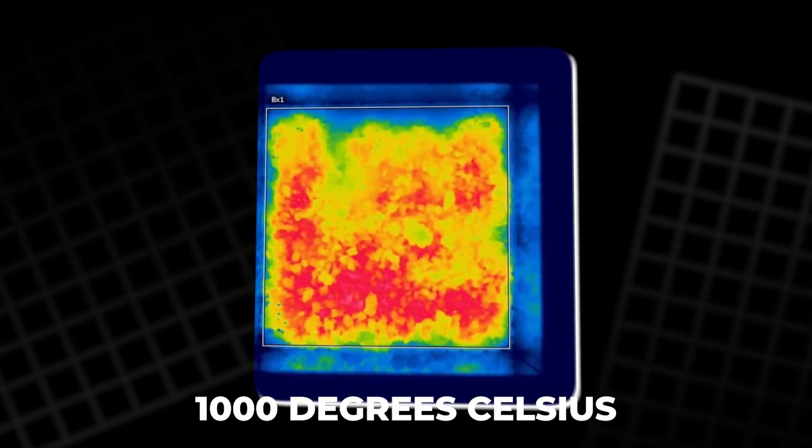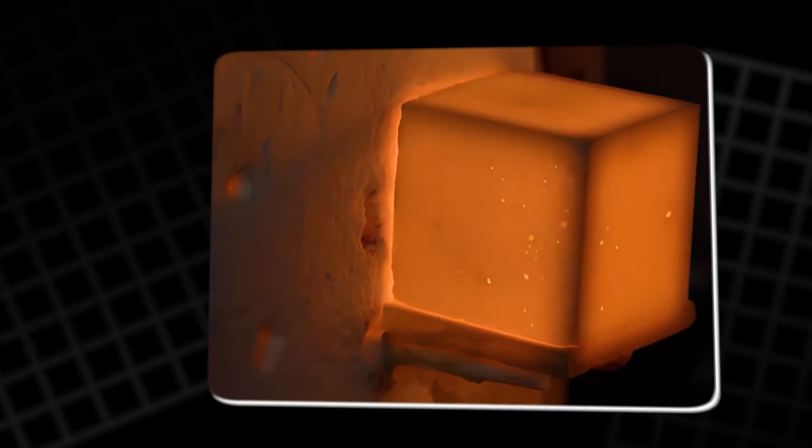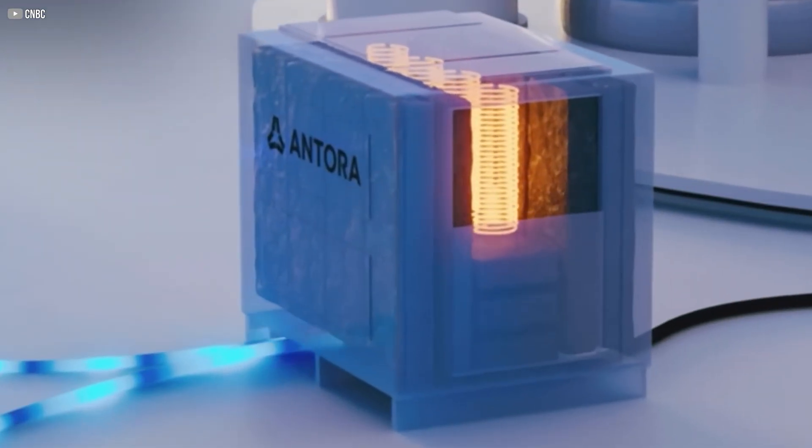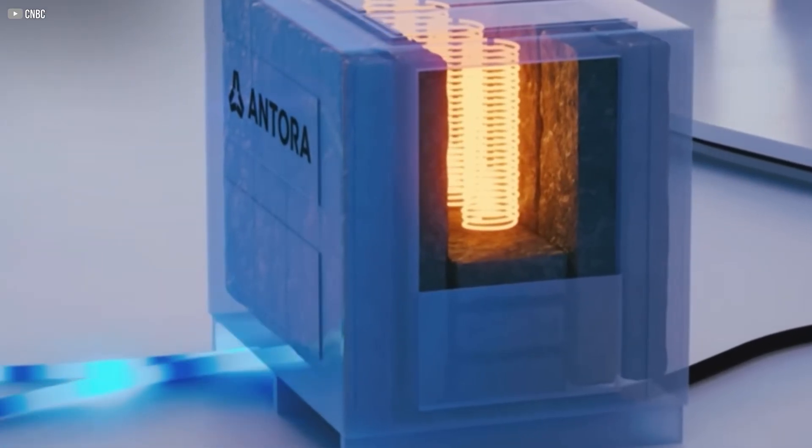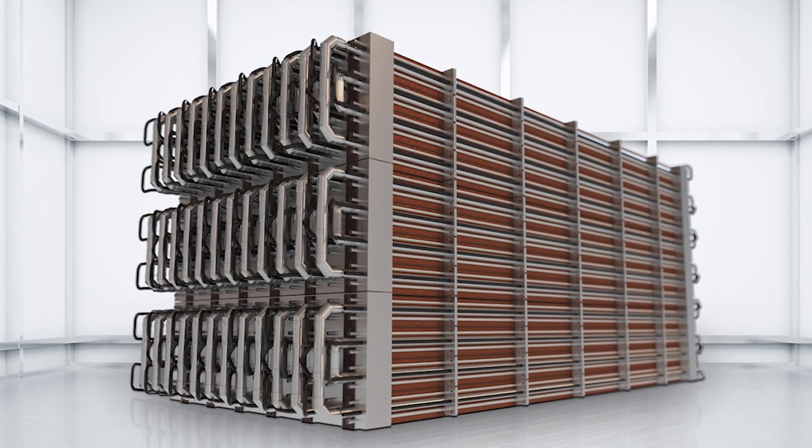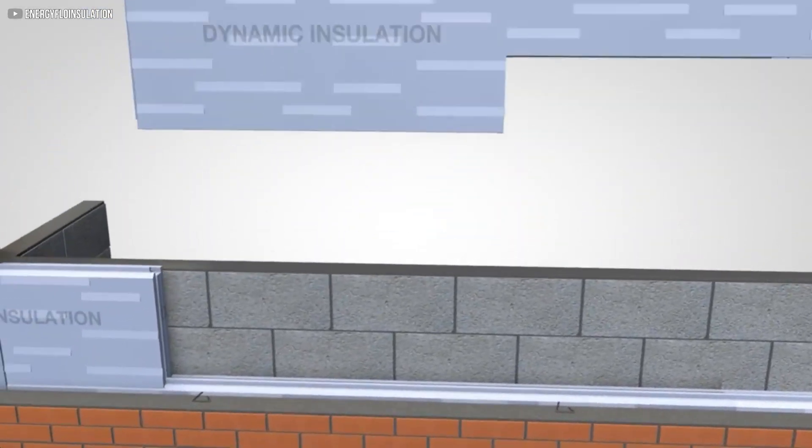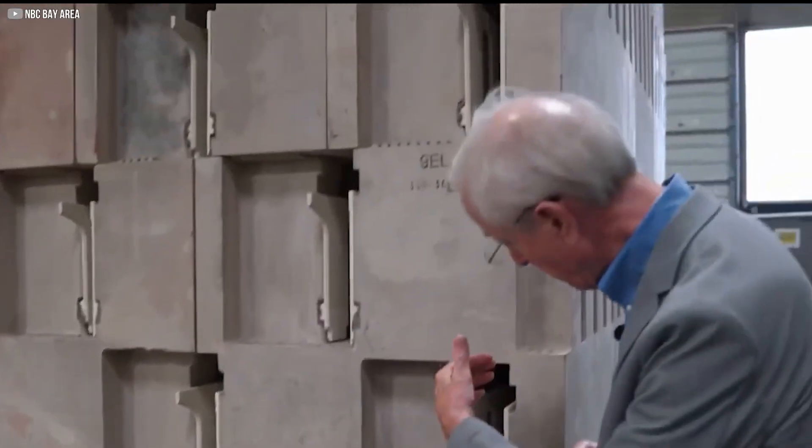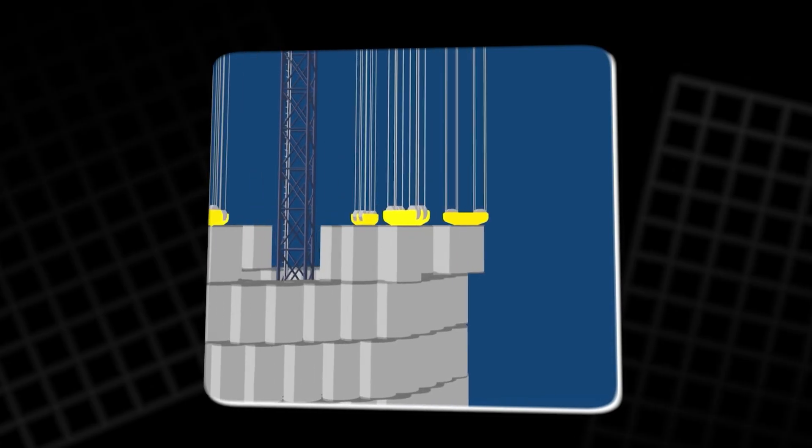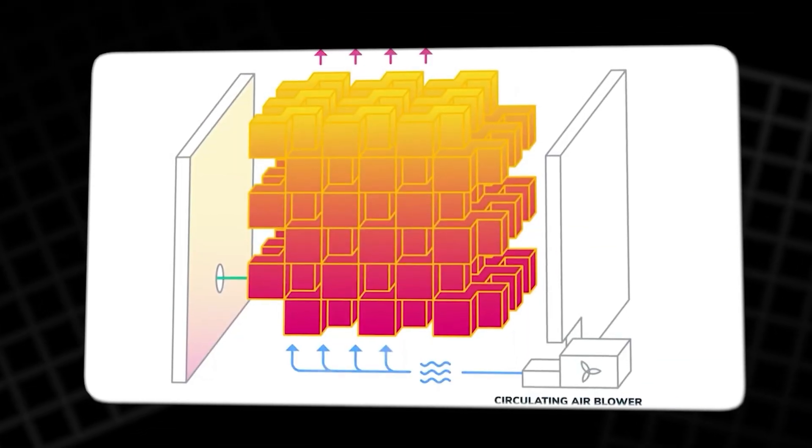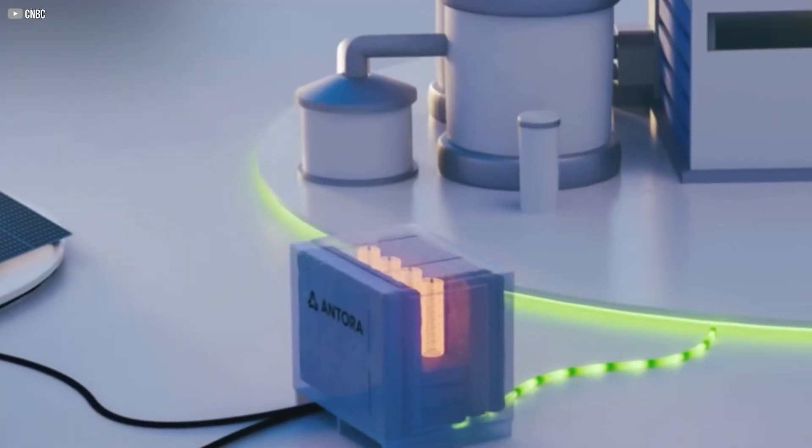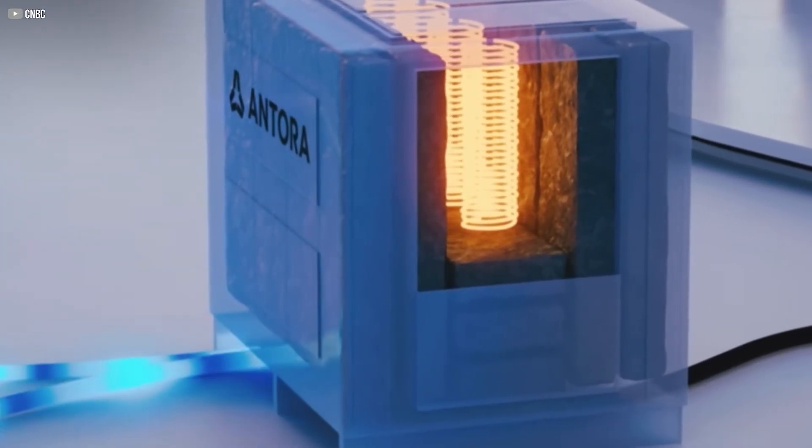Keeping the heat in. Storing heat at over 1,000 degrees Celsius sounds promising, until you think about how easily heat escapes. At that temperature, even the best insulation can fail fast. So how does Rondo keep the heat locked in for hours, even overnight? The answer is dynamic insulation. Instead of just wrapping the chamber in thick materials, Rondo built a smarter barrier. Their system uses a double-wall design with an air gap in between, similar to how double-glazed windows work. But instead of argon gas, this gap contains flowing air. Here's the trick: the air in the gap isn't passive, it moves in a controlled loop around the entire battery before being directed over the hot bricks.